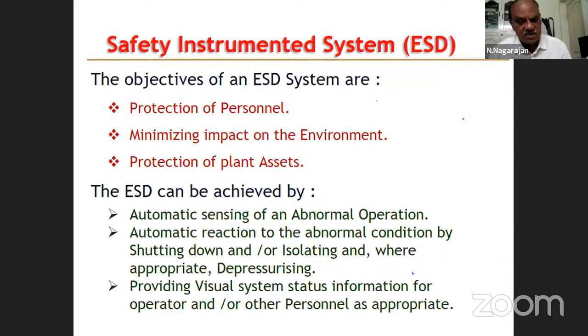Okay. Vessel is isolated. There will be water pouring on the equipment to contain the fire, and sometimes we go to depressurizing. We don't want the hazardous material inside the equipment to remain there. So you depressurize, open the blowdown valves and allow all the hydrocarbons to escape through the flare, not to the atmosphere. Any release from the process unit should be routed to the flare where it will be safely burnt. Of course, it has some air pollution problem, but it will not affect the environment so much.